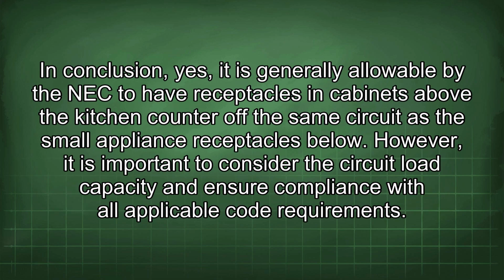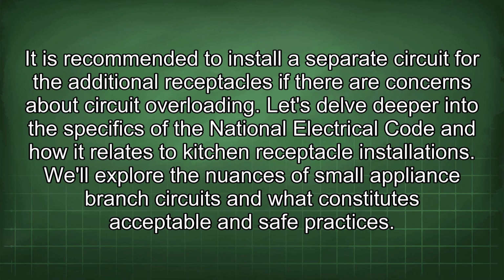In conclusion, yes, it is generally allowable by the NEC to have receptacles in cabinets above the kitchen counter off the same circuit as the small appliance receptacles below. However, it is important to consider the circuit load capacity and ensure compliance with all applicable code requirements. It is recommended to install a separate circuit for the additional receptacles if there are concerns about circuit overloading.